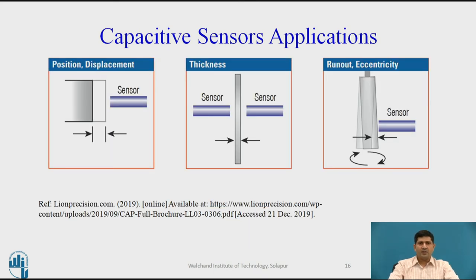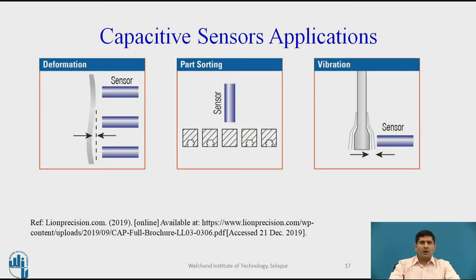General applications of capacitive sensors include position measurement, displacement measurement, measurement of thickness of plates in rolling mills, and measuring runout and eccentricity. Another application is measuring deformations and surface irregularities, overlapping with LVDT application areas. They are also used in part sorting to assess presence or absence of a part, and for vibration measurement, since capacitive sensors support dynamic measurement with a wider application range than LVDTs.